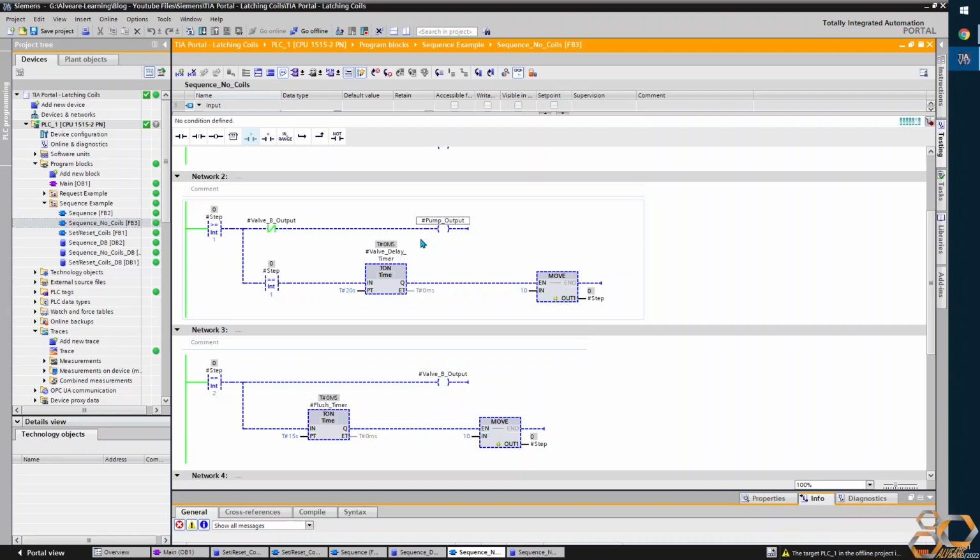You need to sort of think bigger than this example. These devices may be controlled by shared sequences, where you have sequence A through to F, or different recipe batches, or whatever's controlling this. If you have something in another sequence that is setting a coil, and then somebody comes along in a fault situation and just overwrites everything and changes which sequence is now in control, well, that output is still set.